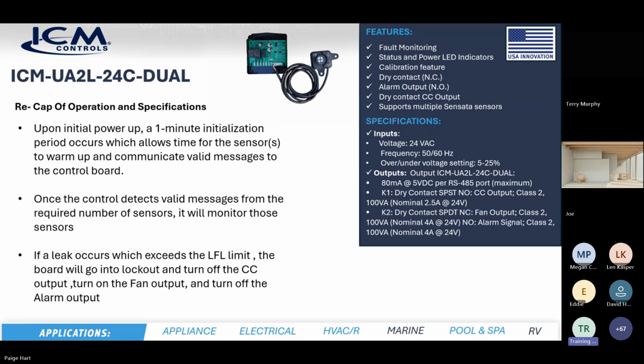So let's talk about how it works. At initial power up, there's a 1-minute initialization period, which basically gives the sensors time to warm up, all right? Because they also use heat in their process, so they have to warm up. And then once the sensors warm up, they're ready to communicate. Once that board gets a valid communication signal back from the sensor, it says, okay, we're ready to go.